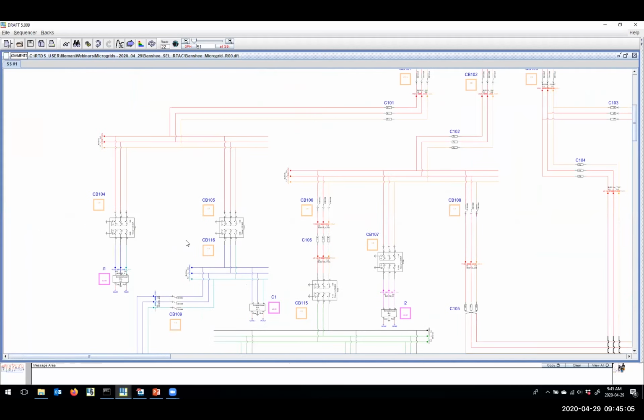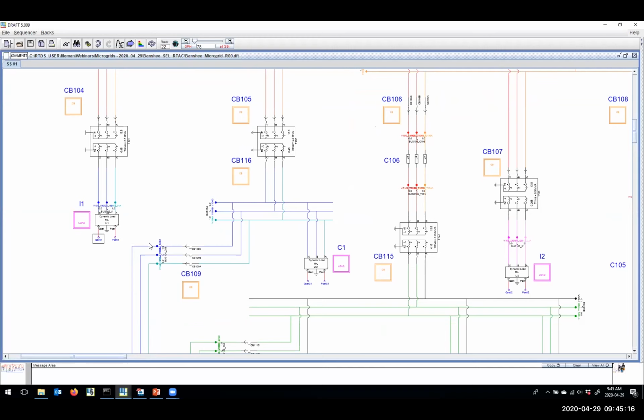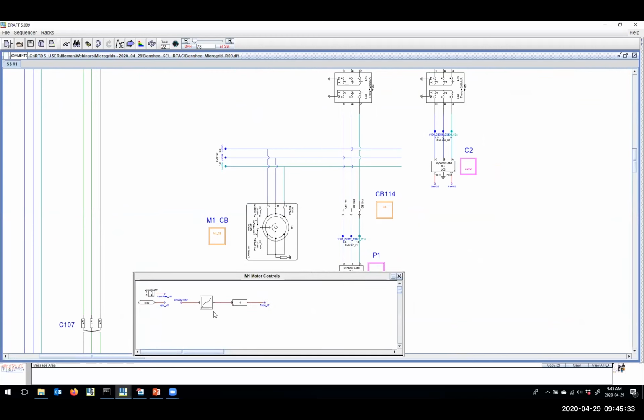So, all of the interruptible, priority, and critical loads are modeled using a dynamic load component. And these dynamic load components allow you to change the amount of power consumed by these loads as the simulation is running. Another thing we can notice in area 1 is our motor load. And our motor load is modeled using an induction machine. And then we can use some control components to enter in the load characteristic of that load for this induction machine.